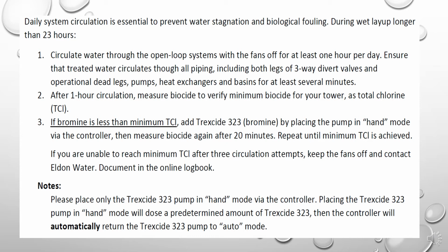Now if you are operating on one of those 7 sites that have chlorine, you actually don't adjust your pumps at all. You want to email Eldon Water, and Eldon Water will make adjustments to your biocide if it is not high enough. You don't want to actually adjust your chlorine pump at all at those towers that have both chlorine and bromine. If you're unable to reach the minimum, whether it's 1 or 2 parts per million, depending on which program you're running, after 3 circulation attempts, you want to keep the fans off and contact Eldon Water, and you want to make sure you document that in your online logbook.